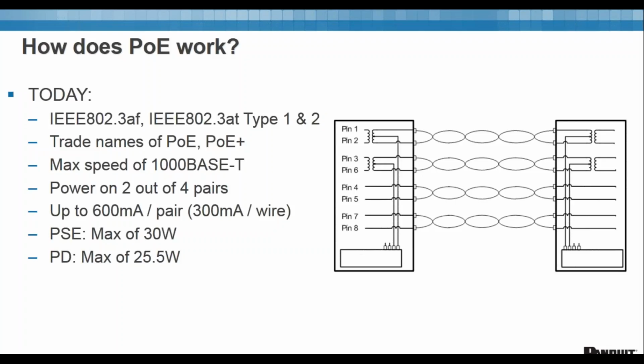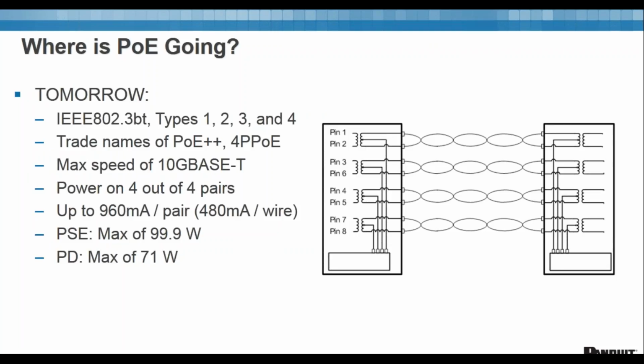This means that only 2 out of the 4 pairs currently get used today to provide the PoE+. PoE today also has a max speed of gigabit or 1000BASE-T, and it only uses up to 600 milliamps per pair. All this adds up, so on the source side at the PSE, there's a max power of about 30 watts, and at the PD, there's a max power of about 25.5 watts. This is good for running stuff like IP phones, some security cameras, some access points.